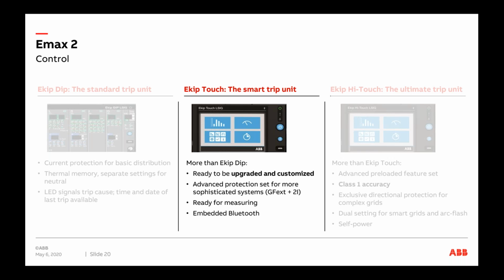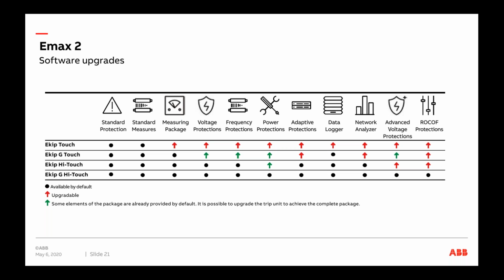Now, even with the eKIP Touch, we have the option or capability to go to the next level, be able to extend any kind of logics or functionality within that breaker, and can be all the way up to Hi-Touch. This slide will probably give you an example of what that means. So the touch in standard comes with standard protection, standard measurements, but can be upgraded with the measuring package and all the other embedded logic packages that we have. eKIP Touch comes with a measuring package and so on. So even an eKIP Touch installed in a plant, which is quite a competitive offering, and then down the line during operation, if the operator or the facility owner decides to have more functionality within the breaker, that's possible even with eKIP Touch, just through software upgrades.